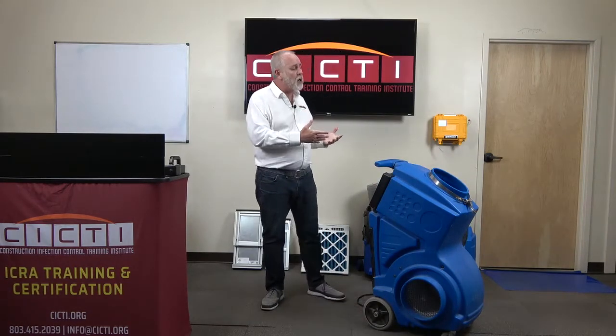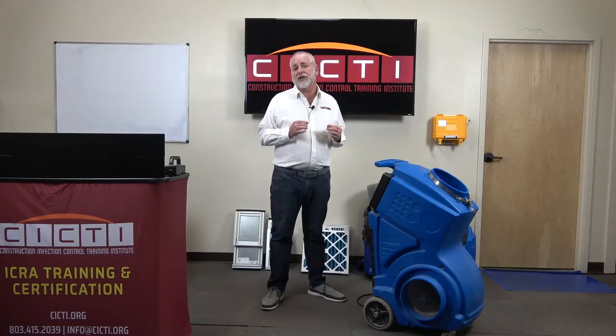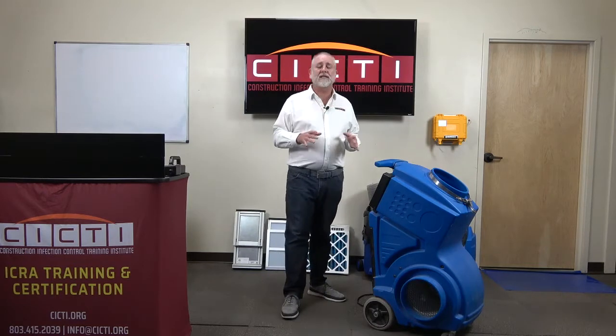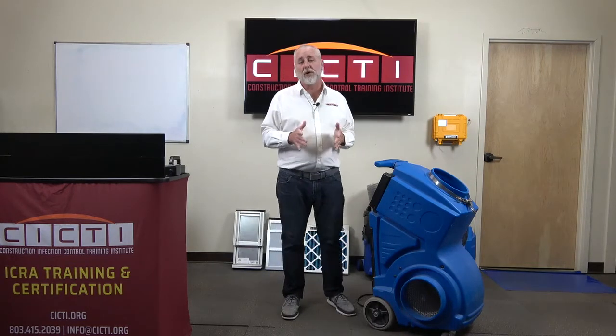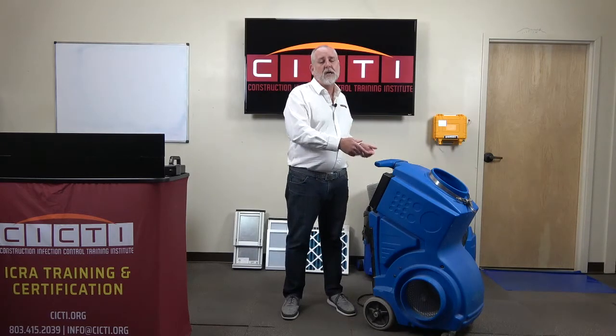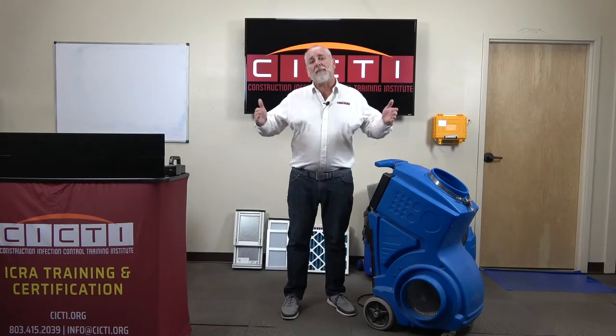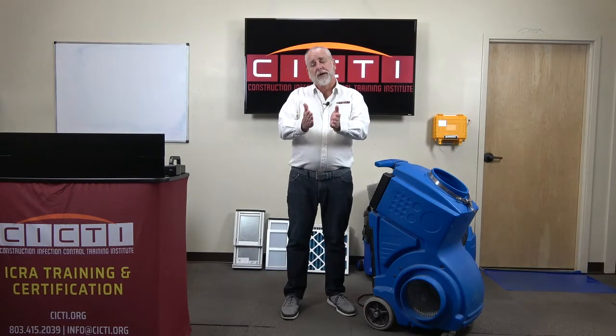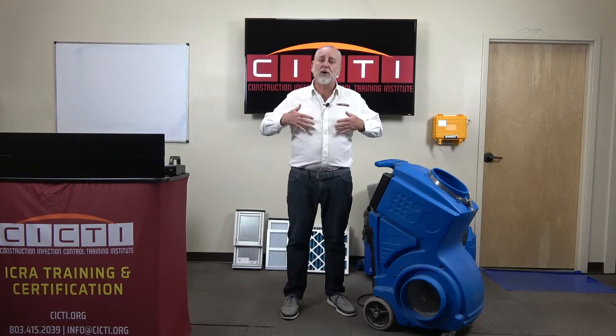Today we want to bring you a video showing you how to test filtration efficiency on your portable HEPA filtered air scrubbers. You may have the best HEPA filter in the world, but if it's not properly installed in this device, we can get what's called bypass around the filter. It's a lot easier for air to go around a filter in a system like this than it is for that air to go through the filter.